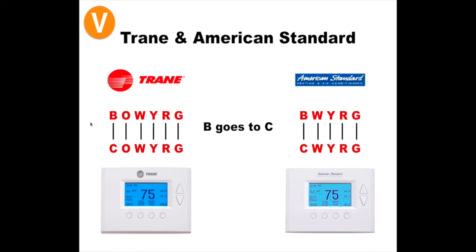Another thing you can do, if you get to the customer's thermostat and they have a B wire connected, is pull the batteries out of the customer's thermostat. If the thermostat stays lit up with no C wire connected, something else is giving it power. If the batteries aren't giving it power and the C wire isn't giving it power, my next step is to check if there's a B wire connected, because that's another possible power wire for thermostats.